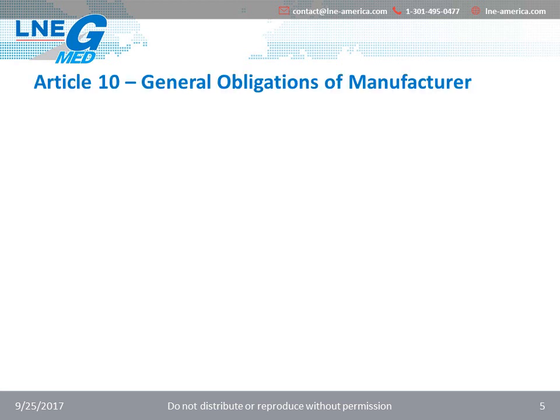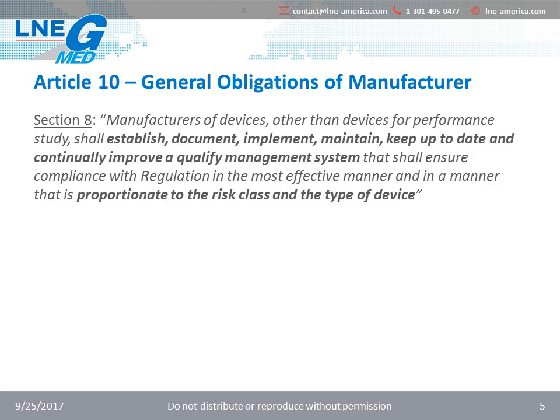In the new European IVD Regulation, Article 10 covers the general obligation of the manufacturer. Among those obligations, the legislator included QMS requirements, which are presented in Section 8. The first paragraph of Section 8, which is presented here, states that the manufacturer shall establish, document, implement, maintain, keep up to date, and continually improve a quality management system, and it also adds the notion of risk in the implementation of processes related to the quality management system.